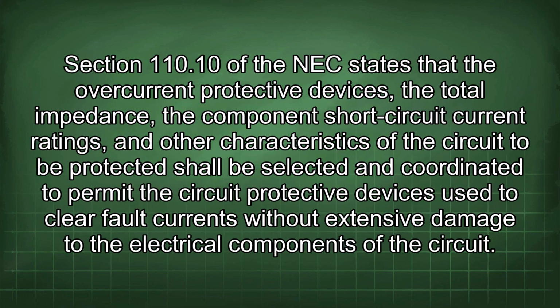Section 110.10 of the NEC states that the overcurrent protective devices, the total impedance, the component short circuit current ratings, and other characteristics of the circuit to be protected shall be selected and coordinated to permit the circuit protective devices used to clear fault currents without extensive damage to the electrical components of the circuit.